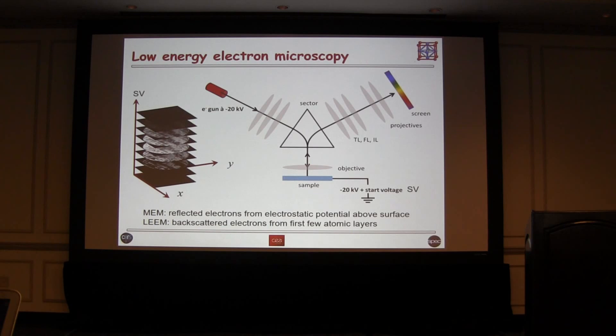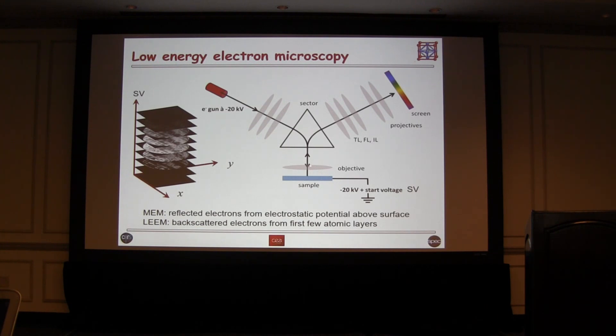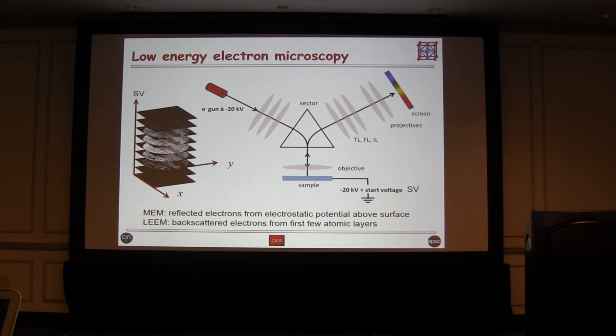To detect the polarity directly, we'll be using a technique we've been developing for a while and applying it to charged surfaces: low-energy electron microscopy. This is a schematic of the instrument. You have electrons accelerated at 20 kilovolts through a series of lenses. They go through a magnetic sector field in order to send these electrons perpendicular to the sample surface. Just before the sample surface, they are decelerated. The sample itself is virtually at the same potential, with a very slight difference called the start voltage.